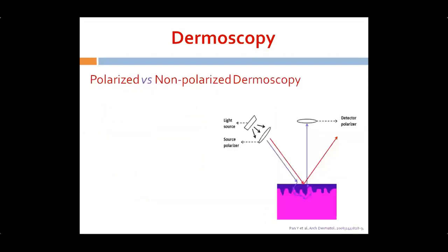Coming to polarized and non-polarized dermoscopy. In polarized dermoscopy, the polarized illumination mode is employed. And in polarized dermoscopy, there are two sets of polarizers. One is the source polarizer and the other is the detector polarizer, as you can see in this image. The source polarizer polarizes the light emitted from the light source.